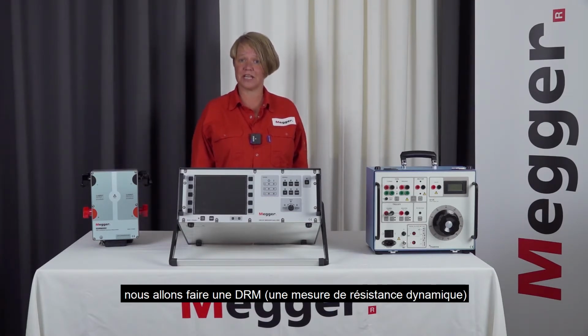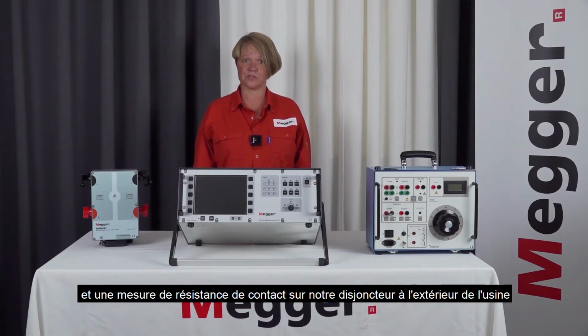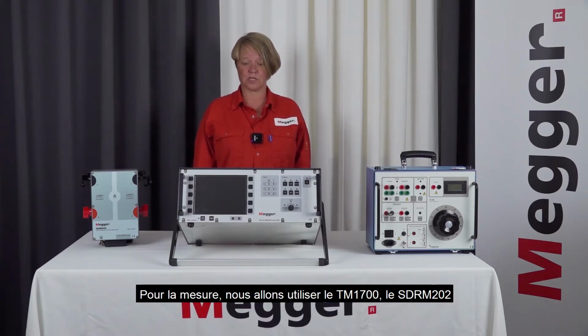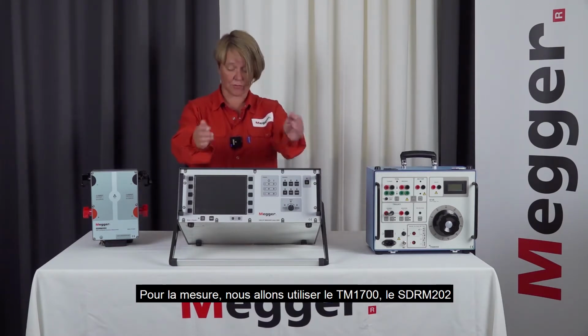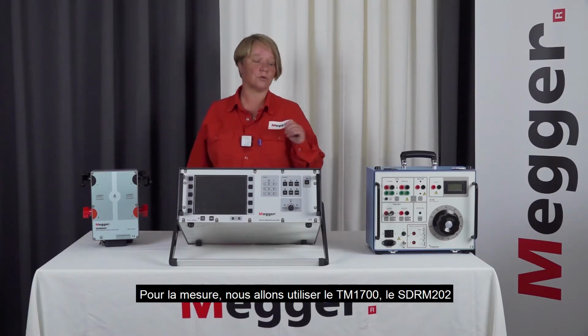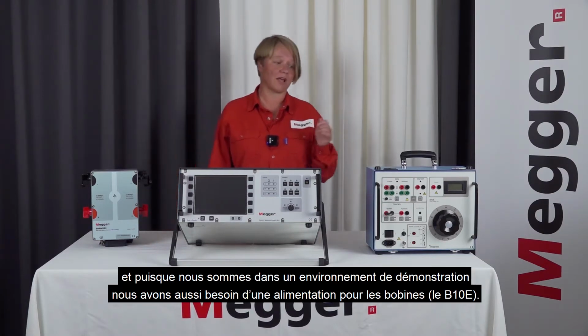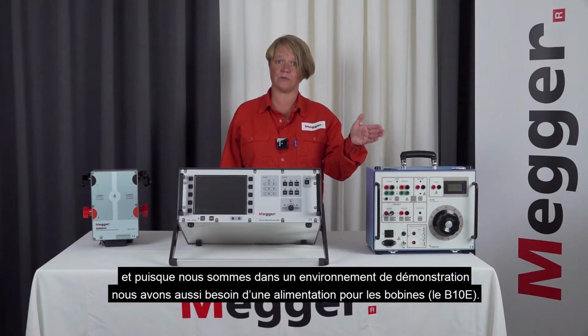Today we're going to do a DRM, a dynamic resistance measurement, and a contact resistance measurement on our outdoor breaker outside the factory. During the measurement we're going to use TM1700, SDRM202, and since we are in the demo environment we also need the power supply for the coils, a B10E.